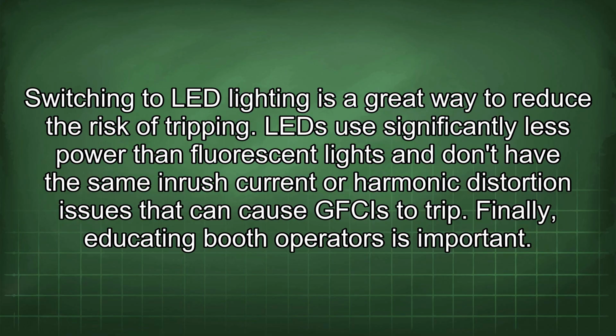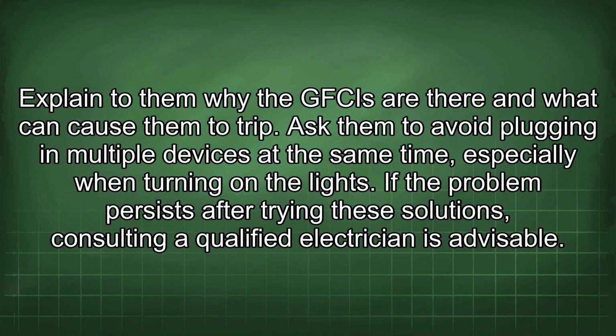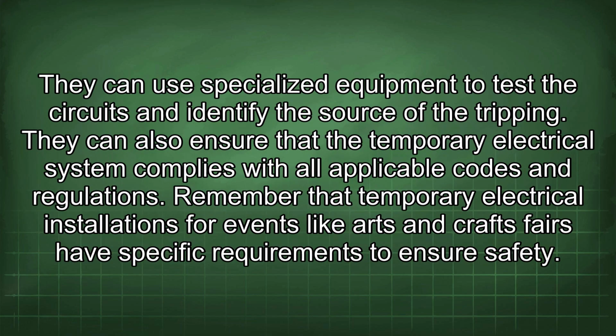Finally, educating booth operators is important. Explain to them why the GFCIs are there and what can cause them to trip. Ask them to avoid plugging in multiple devices at the same time, especially when turning on the lights. If the problem persists after trying these solutions, consulting a qualified electrician is advisable. They can use specialized equipment to test the circuits and identify the source of the tripping. They can also ensure that the temporary electrical system complies with all applicable codes and regulations.